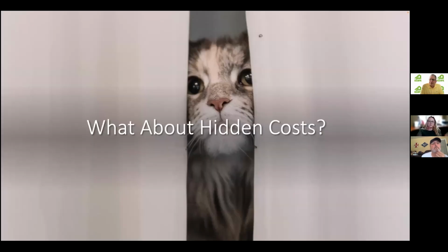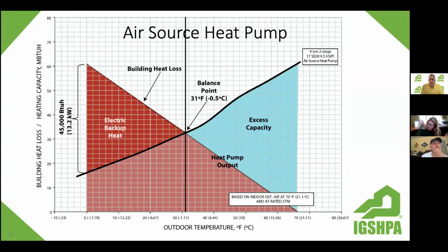There are always hidden costs that we have to consider, and these sometimes are not obvious. But if we're comparing the air source heat pump in particular, we could certainly affect the amount, the components, the electrical system, labor, wiring, a lot of costs there that aren't always discussed. I like these charts. They kind of show what happens over the course of the year in the heating mode. And this one is an air source heat pump. I have a geothermal heat pump coming up that will compare. I pulled this curve out of the manufacturer's data. So this is published data. You can find it on the website.